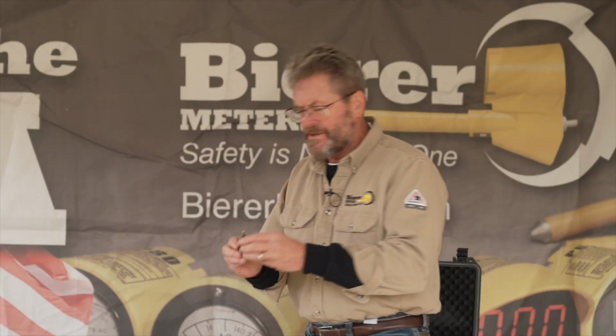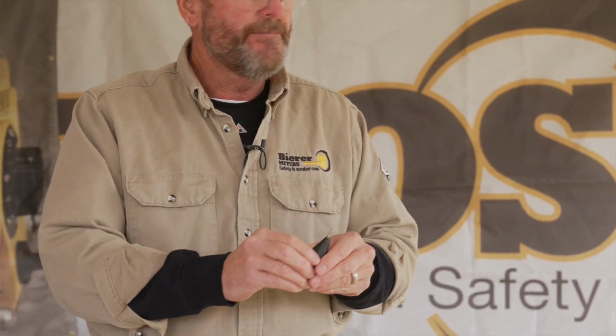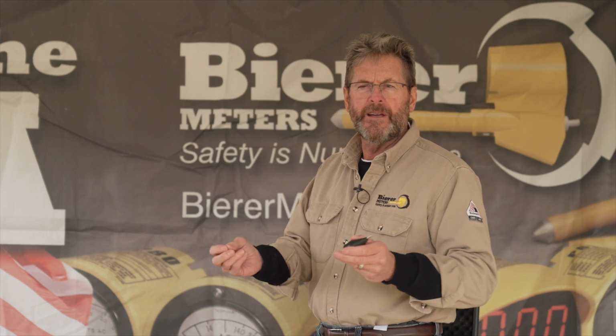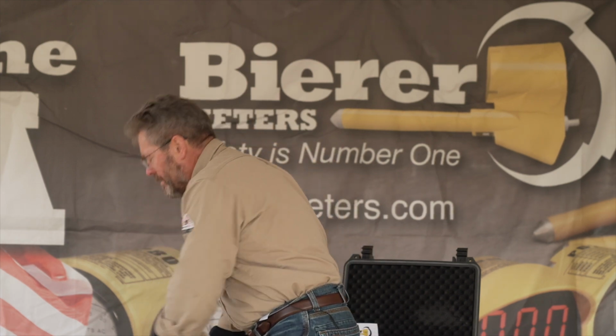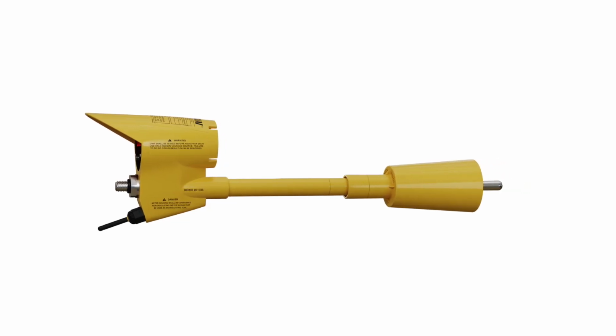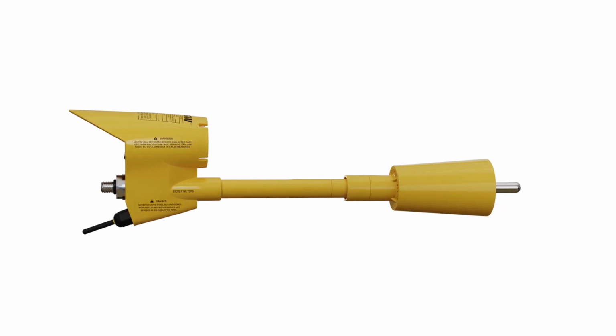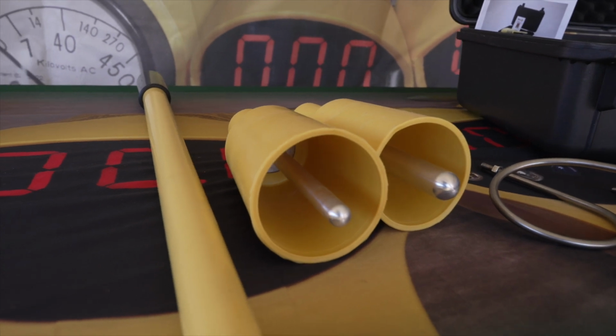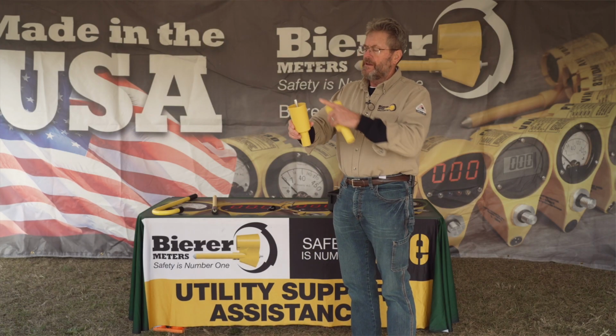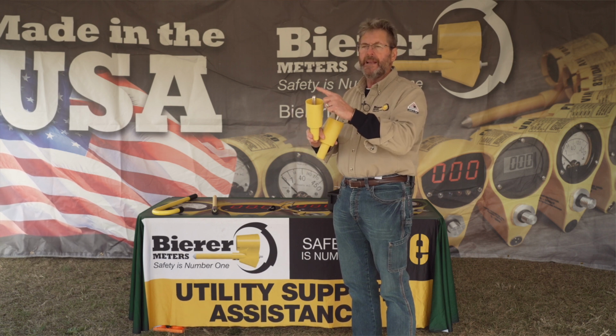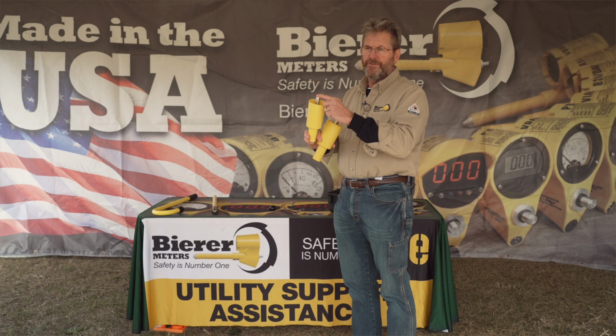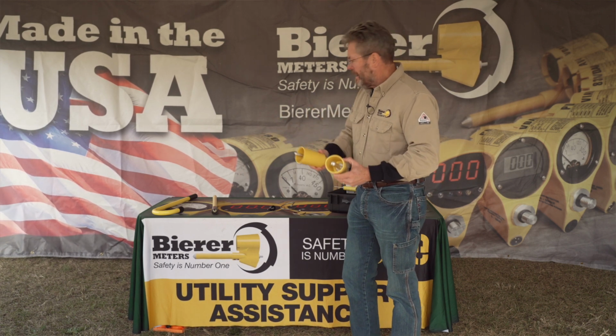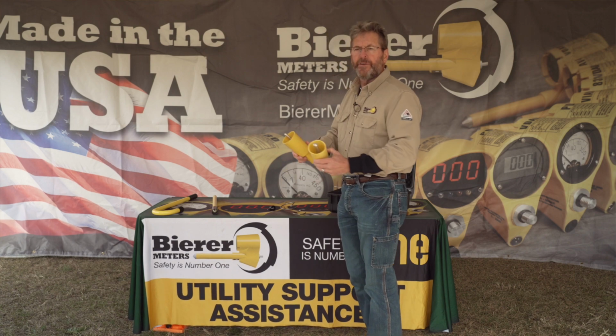We also have another straight probe that's shorter. Maybe you're going to be going to capacitive test points quite often, or just in scenarios where you have less space to work with. And if you're working underground, you're going to want to add the bushing adapters to your meter. So we have the 15/25 kV interface, and then we also provide an accessory with the 35 kV interface on your bushing adapter. You want to add these to your kits if you work underground or a combination of overhead and underground.